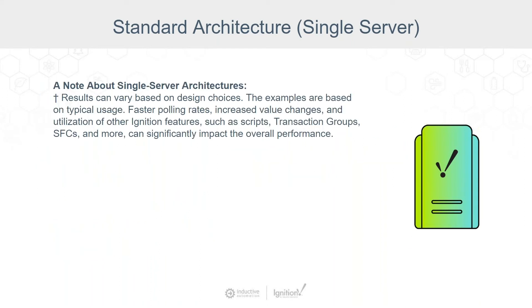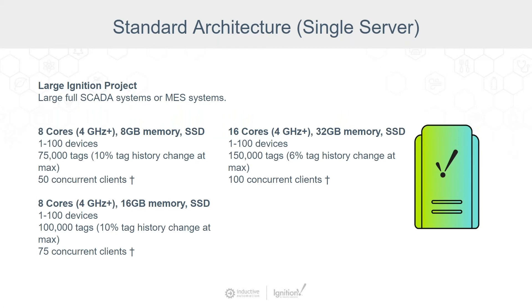Another question: what's the most significant resource factor — devices, tags, or clients? For example, one to five devices, 100,000-plus tags, one to five clients — is anything more significant than the others? The devices depend on device type. Modbus devices are really lightweight, while Allen-Bradley protocol drivers are more heavyweight. OPC UA devices can be even heavier if they're updating constantly, but if subscribing to a Siemens S7-1500 with tags that aren't changing, it becomes lightweight because OPC UA is a subscription-based protocol.